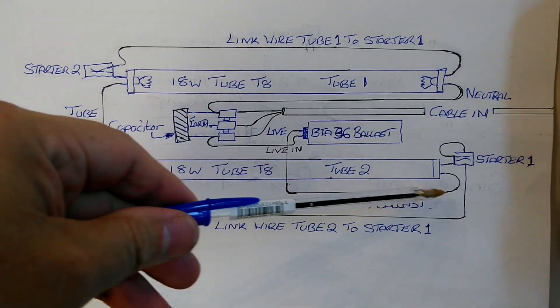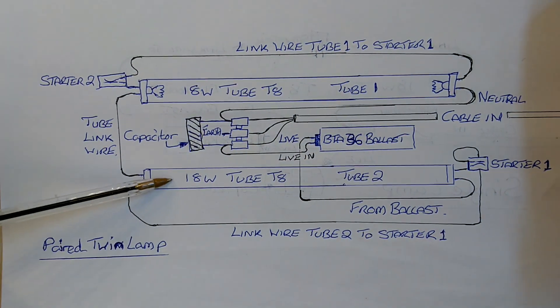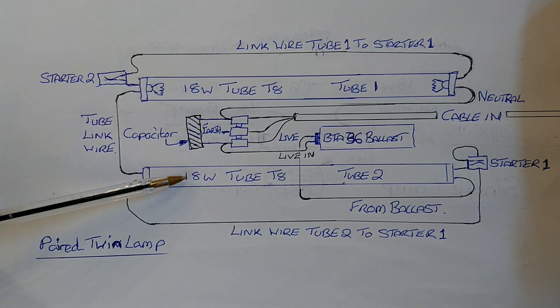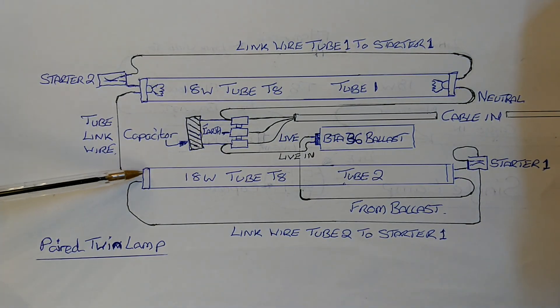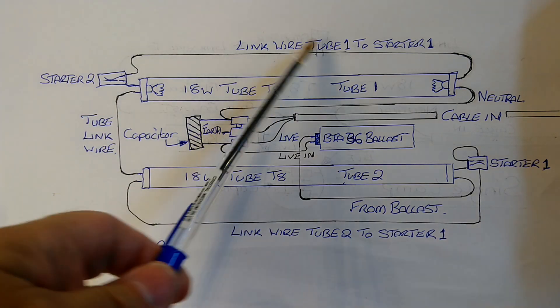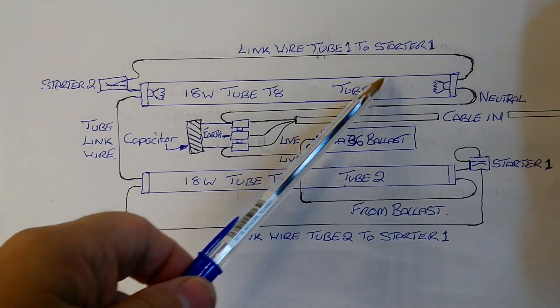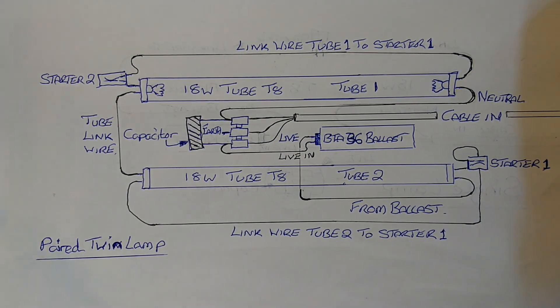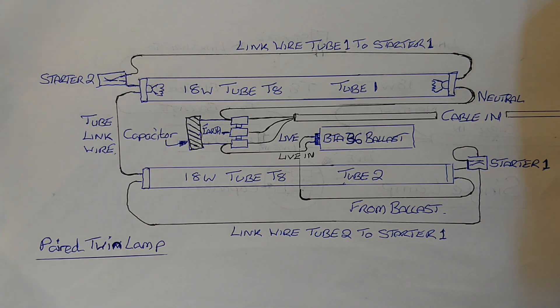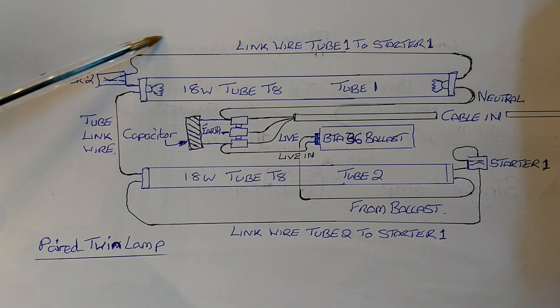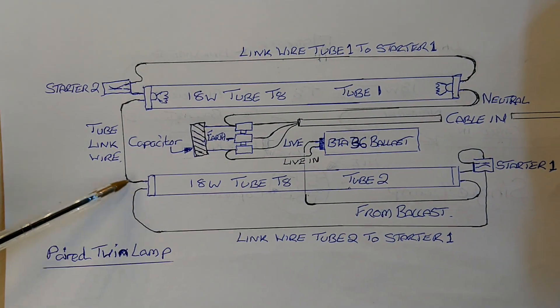And it comes out of the ballast, goes into tube number two. From tube number two there is a link wire which goes to tube number one. And then from tube number one it then goes back as a neutral wire back to the connector block. The other wires are two series pair starters, and these are connected with the other pins on the first light, again tube one and tube two, as follows.